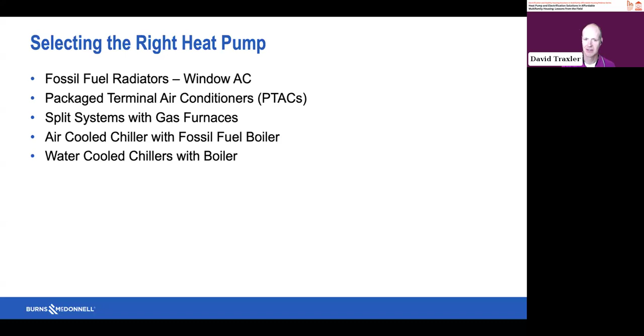So now that we've covered some of the fundamentals, what heat pump is going to work for your building? We're going to talk about a few: fossil fuel radiator window AC systems, if you have those, what do you do? Packaged terminal air conditioners, similar to what you see in hotels under the windows. A split system with gas furnace, which is what most of us have in an apartment or home. And an air-cooled chiller with fossil fuel boiler, for larger multifamily buildings with hot water heating and chilled water cooling. Some buildings I've worked on have also had water-cooled chillers with fossil fuel boilers. We're going to address each one of these.